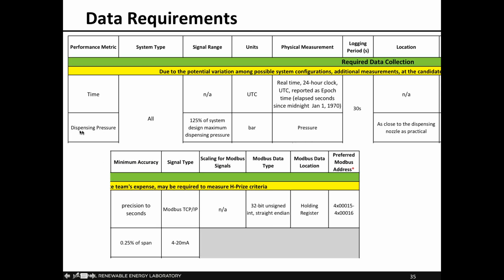Then you see the dispensing pressure. We'll need the pressure at the dispenser as it goes into the vehicle, located as close to the nozzle as possible. That will come to us as a 4 to 20 milliamp signal. That's an isolated signal, so any of the signal wiring cannot hook up to your system at all. It needs to come directly to the DCS. And that's so we can verify the information that comes out of your PLC.